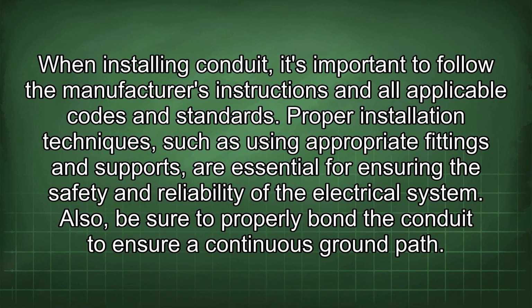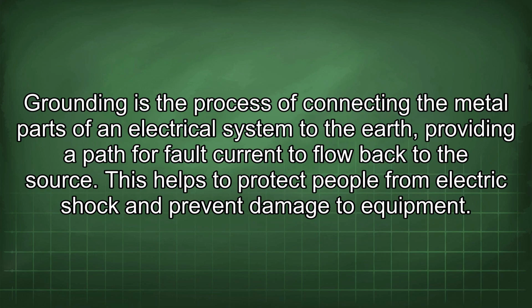When installing conduit, it's important to follow the manufacturer's instructions and all applicable codes and standards. Proper installation techniques, such as using appropriate fittings and supports, are essential for ensuring the safety and reliability of the electrical system. Also, be sure to properly bond the conduit to ensure a continuous ground path. Grounding is the process of connecting the metal parts of an electrical system to the earth, providing a path for fault current to flow back to the source. This helps to protect people from electric shock and prevent damage to equipment.